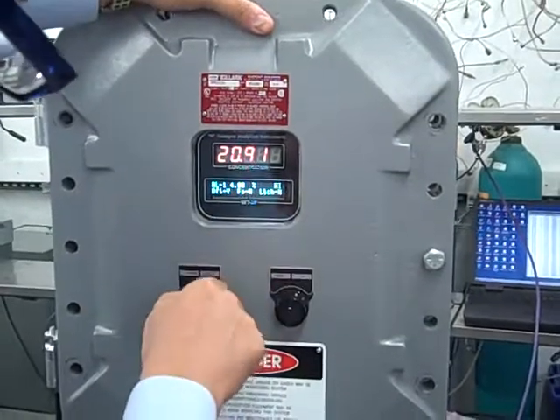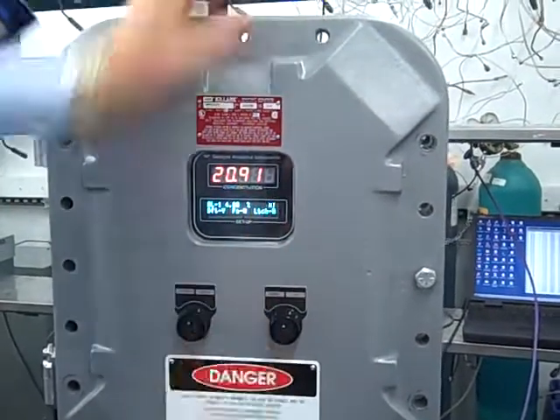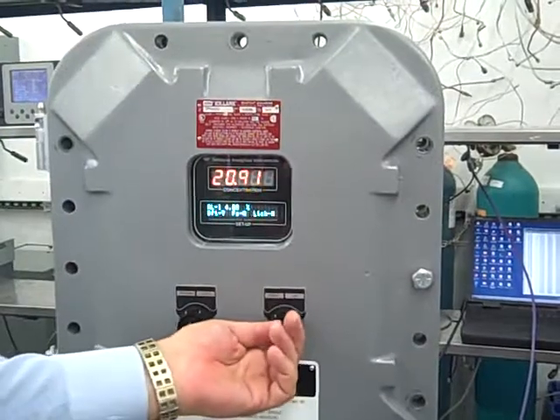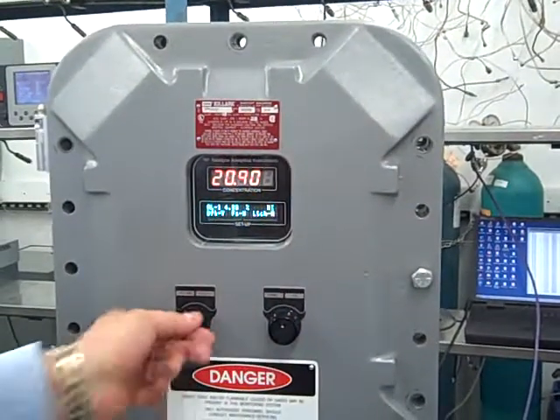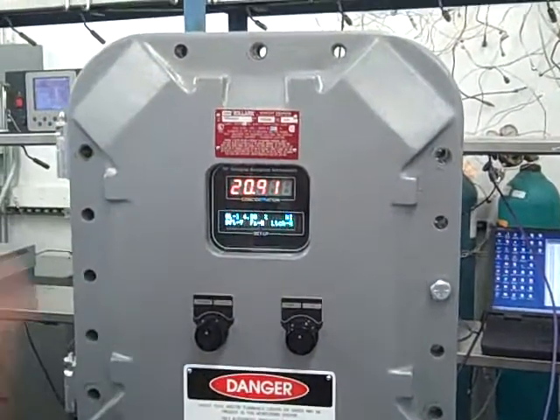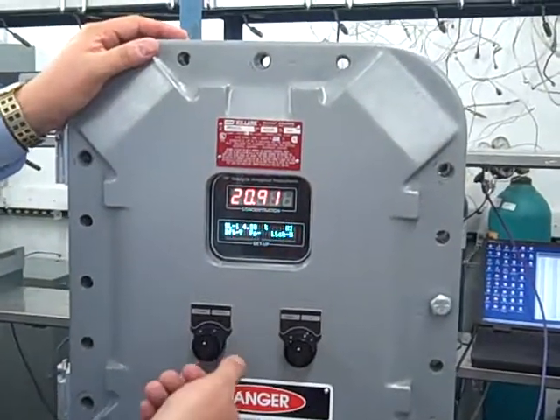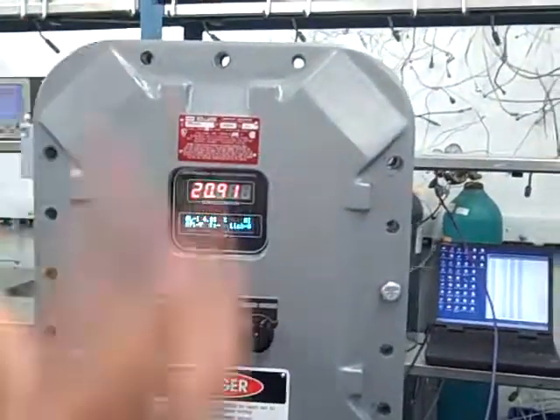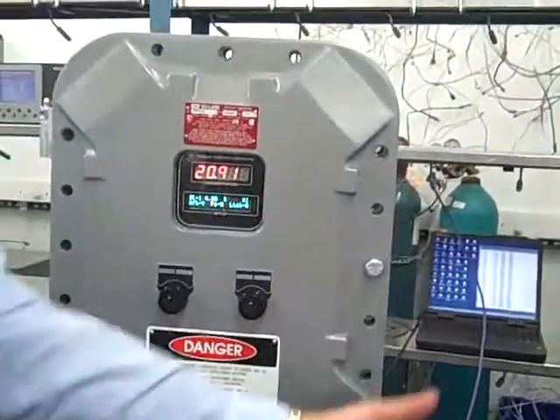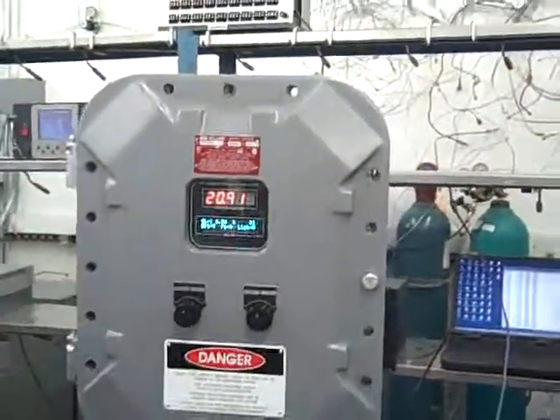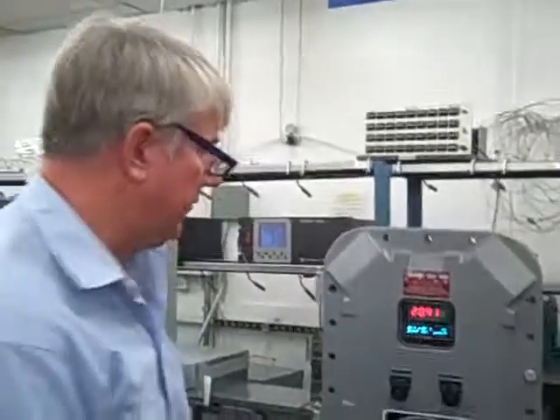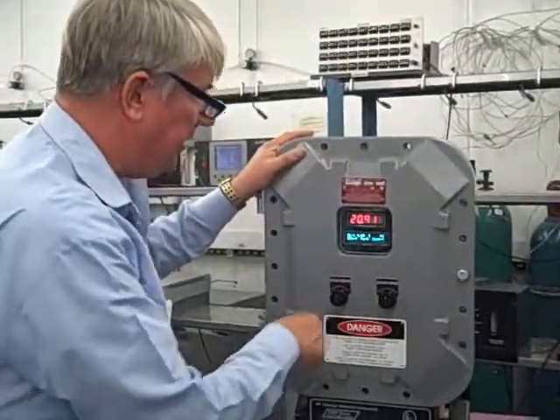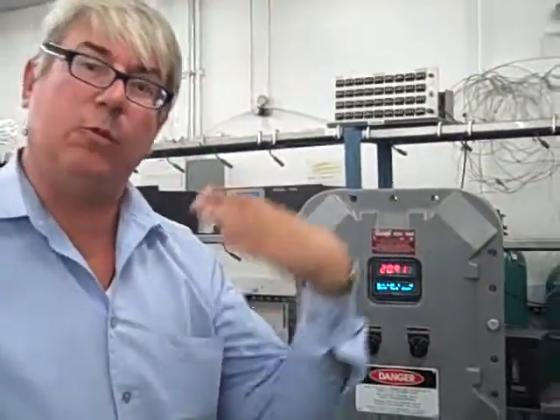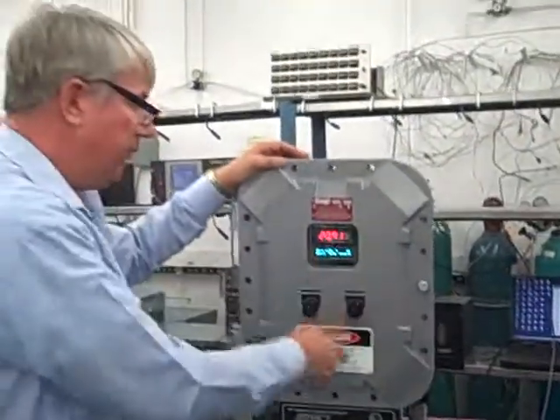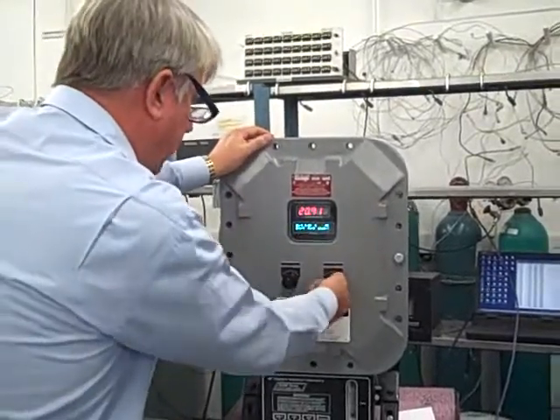I can say it's a high alarm or a low alarm. Notice I've changed it from high to low, back. I can defeat the alarm, which means the alarm isn't active no matter what happens. I can make it fail-safe or non-fail-safe, so that fail-safe means when the power goes off, the state of the alarm switches. So you see the power loss event. And latching means that even if the alarm condition goes away, the relay stays in that state until you unlatch it. So very straightforward, easy to configure the alarms any way you want them.